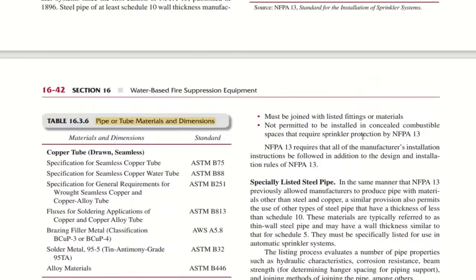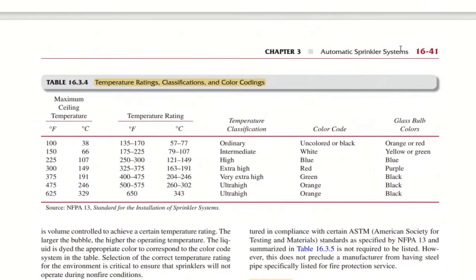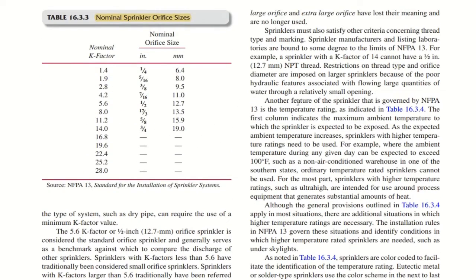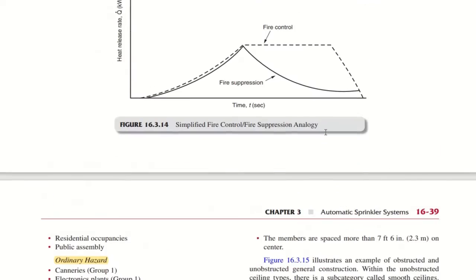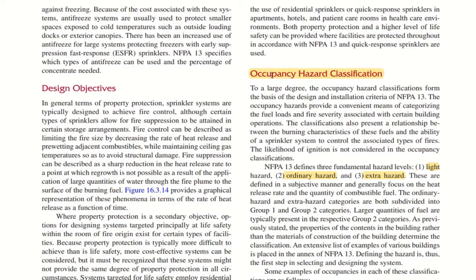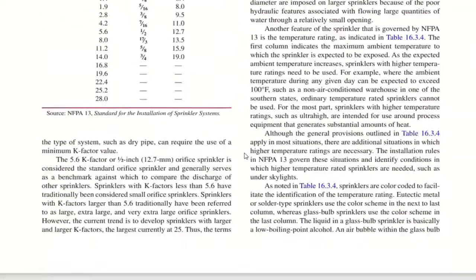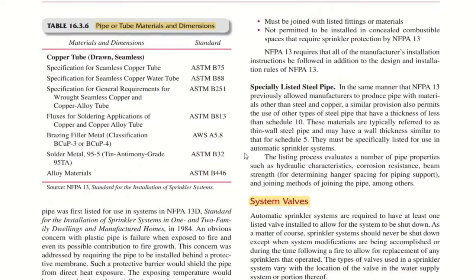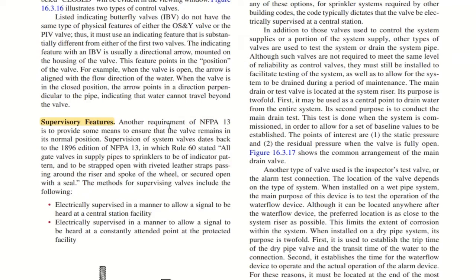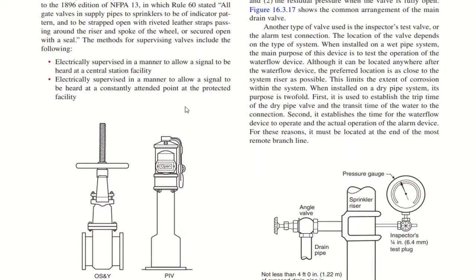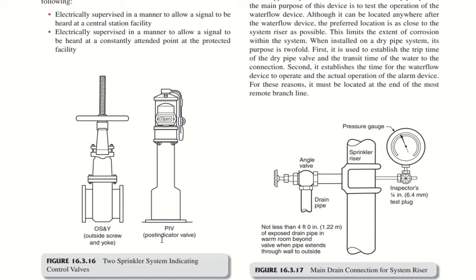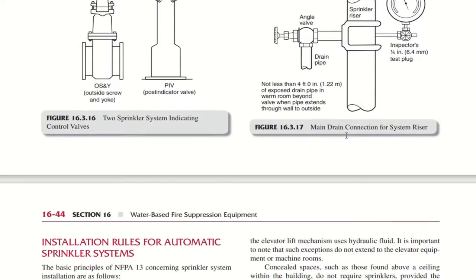So basically this automatic sprinkler system chapter 3 covers types of systems like wet, pre-action, deluge, and also dry type systems. Apart from that, it also covers the nominal sprinkler orifice sizes, ceiling construction types, and also the main important topic, occupancy hazard classification. Apart from that, this covers various system components such as pipes and valves. In valves you have supervisory switches as well. This is OS and Y gate valve, post indicator valve. So you can check my video series on NFPA 13 for more details about these components.